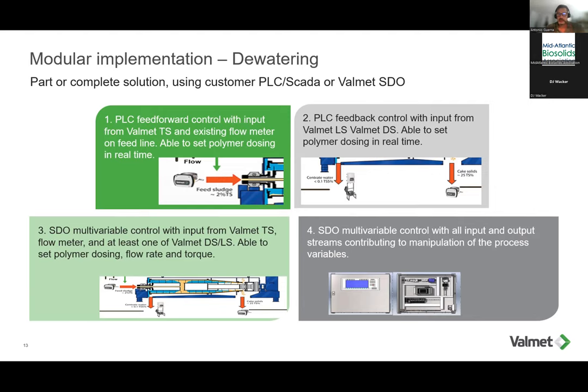Now, by adding a second measurement, whether it's a centrate measurement or a cake measurement, you can further implement controls by having both a feed forward strategy based on what's coming into the system and a feedback strategy based on one of those two streams. Now you can take it one move further by having those three measurements. In this particular case, we're able to optimize or manipulate more variables. By having multiple measurements, we're still doing the polymer dosing and the flow rate, but now we can start also controlling torque. So that is the complete package.